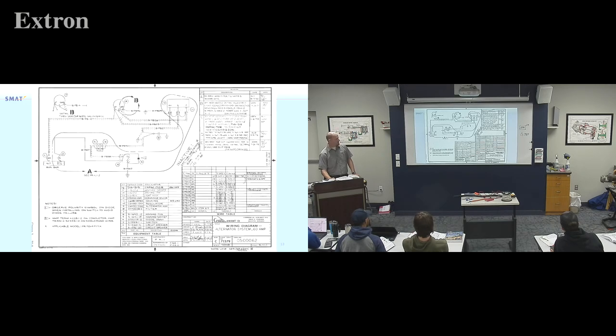If I go pick another one for the fun of it, PA13, I can find it, there's 15, 16, PA13, hard to read on the computer, but I believe that's 18 gauge. So if you look for the GA on the key and just scroll up to whatever wire you are, that'll tell you the gauge. That's the easy way, and that's what you should actually do as a mechanic. If you get into the chart we're going to go over shortly, I'd say you did something wrong, or you're at A&P school - it's one or the other. That's generally where we're going to go with those two.